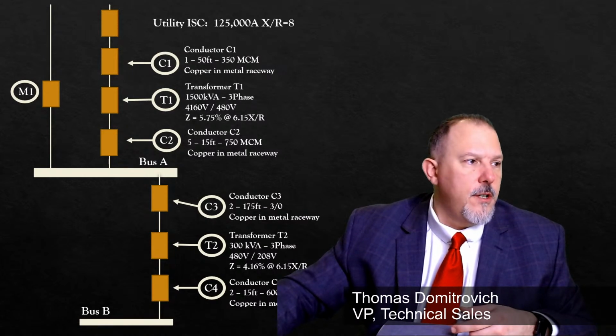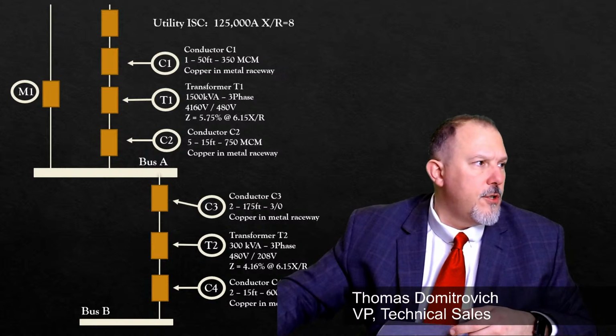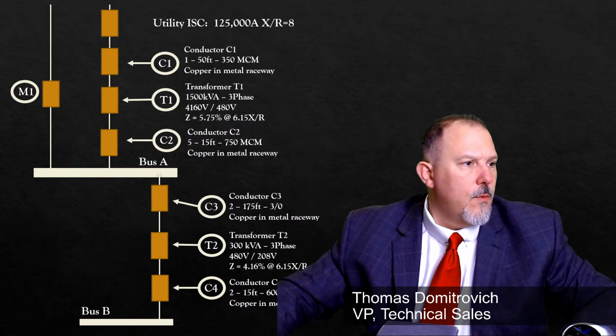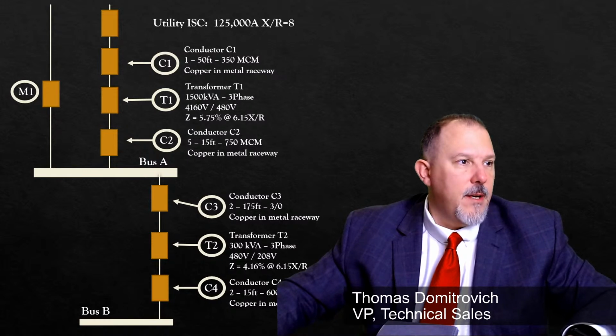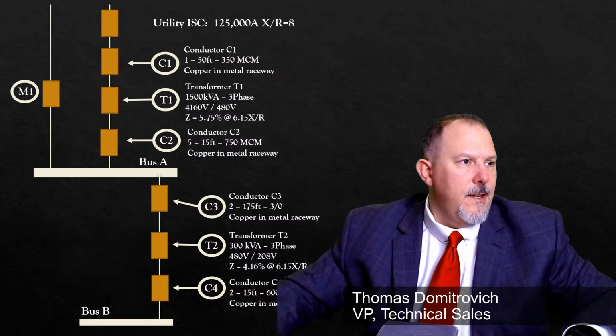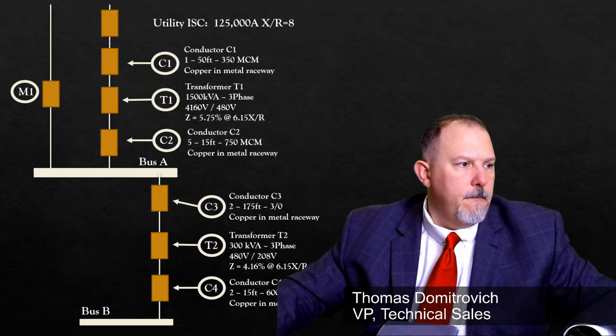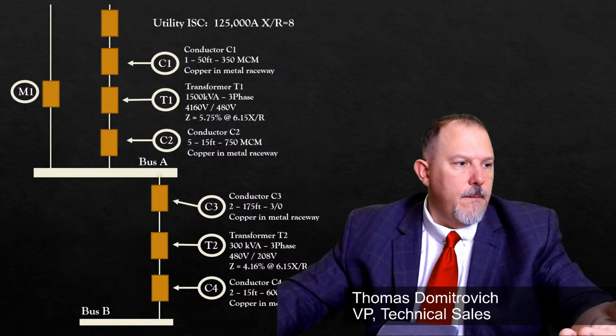So motor contribution. I'm looking for fault currents, short circuit current calculations. So I'm going to see, there are some rules of thumb that we follow. Motor contribution, okay, types of short circuit currents, base equations. If I had my book here, physically, I'd find it. Impedance elements. Positive, negative, zero sequence, all that good stuff. Basically, the rule of thumb is search for motor. So they give you some assumptions for impedance values. They give you some assumptions for grouping.